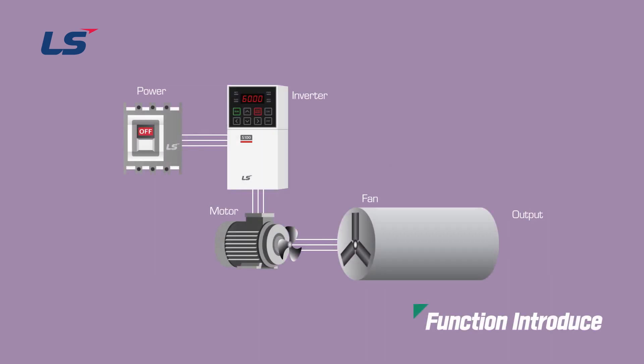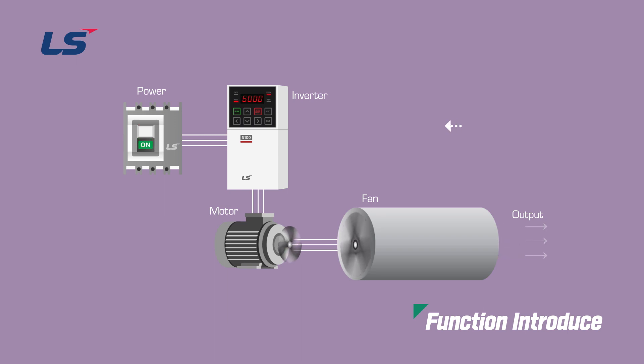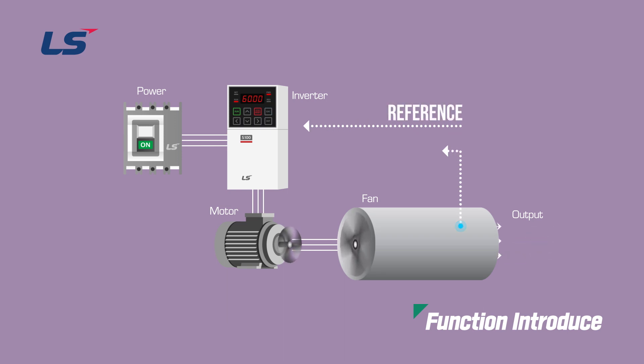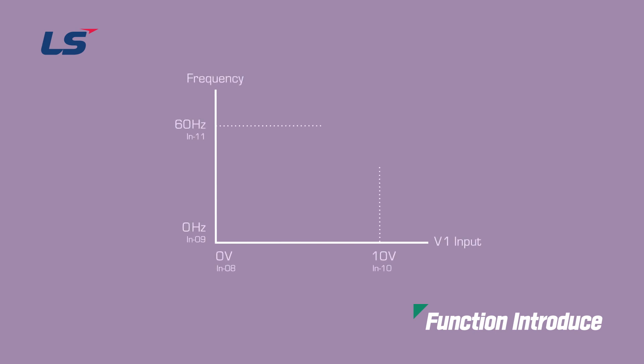Analog voltage and current input through the AC drive control terminal can be used for various commands such as operating frequency setting or torque command, and can also be used as feedback during PID control. However, the minimum and maximum values of commands or feedback may vary depending on the load system.